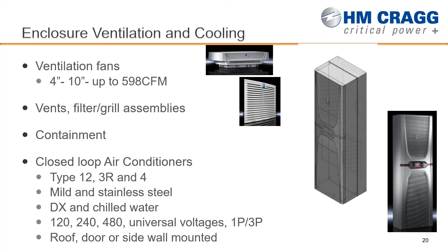We talked a moment ago about some of the other problems that you face besides heat dissipation. The other big thing is the potential to have hydrogen gas vented into the cabinet, especially when we're talking a type 4, which is sealed. It's completely sealed away from whatever the ambient environment is. So if for whatever reason the batteries were to start venting, there's really no way unless we take some kind of mitigation to eliminate that problem.